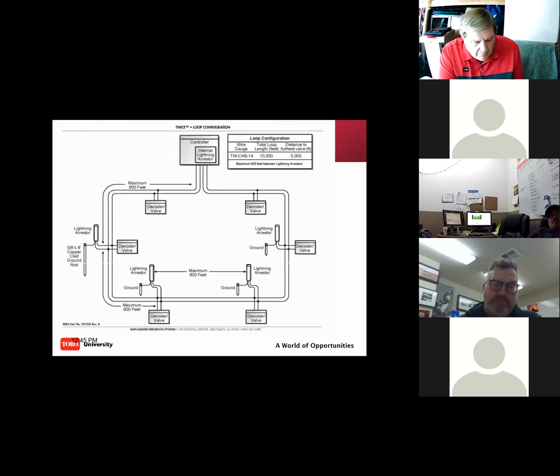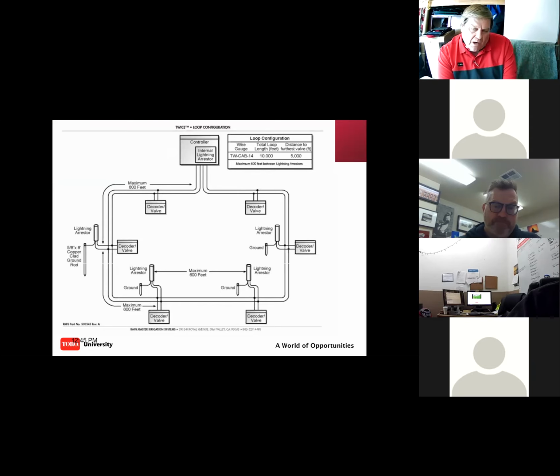As you work your way down the line, you'll find the decoder that has the high current draw, as I did in this photo here. So that's what we're doing. You're just walking through the system, moving your way down the 2-wire path where you can. If you have a looped system, in this example here, remove the loop from the clock. So I'm only following one 2-wire path itself.